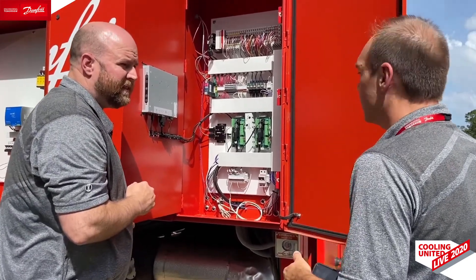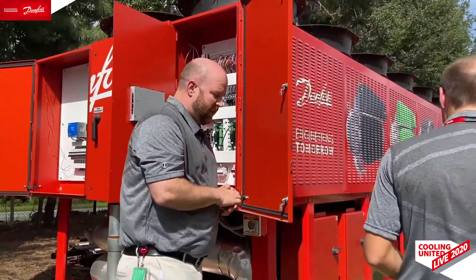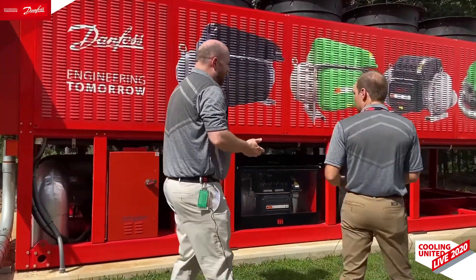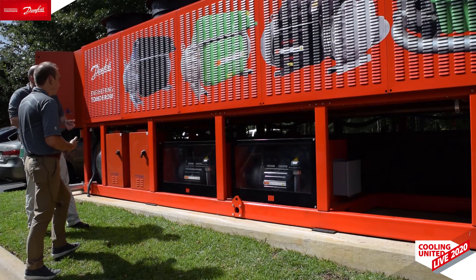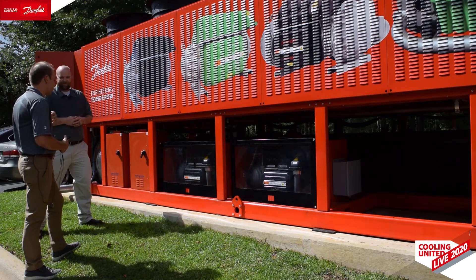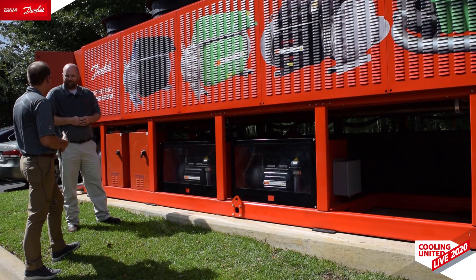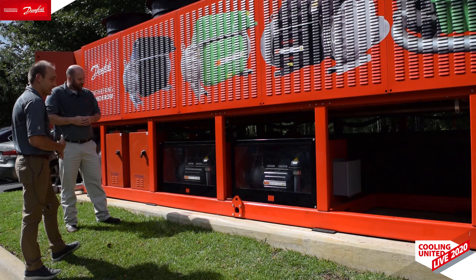What compressors do we have on this chiller? This chiller has two of our new TTH-375 compressors — they're a little more than what our climate requires; we could actually get away with the TT-350 for this building. However, it gives us the ability to showcase these new compressors. The TT-350 would definitely do the job, but even with 100-degree days here in Florida — about 38 Celsius — this is a bit more than we'd need. They really do look nice.